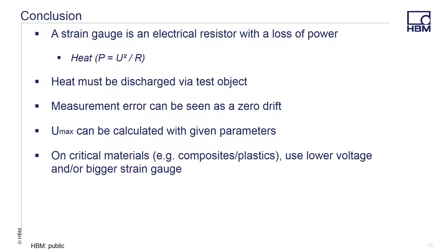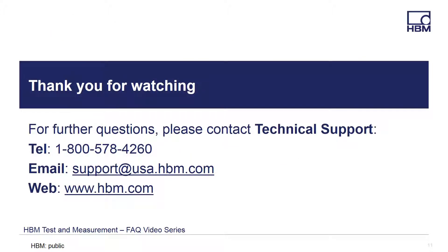To conclude, we discussed the fact that a strain gauge is an electrical resistor with a loss of power, and the heat generated must be discharged in some manner. Excessive heat can cause measurement errors seen as zero drift. The maximum excitation voltage applied can be calculated using certain known parameters. When using certain materials such as composites or plastics, you should either use a lower excitation voltage or choose a larger strain gauge. If you have any questions, please feel free to call, email, or visit our website for the latest products, solutions, and downloads at www.hbm.com. Thank you.